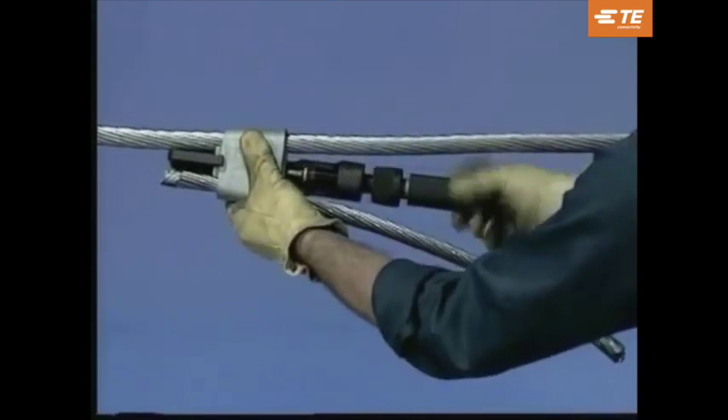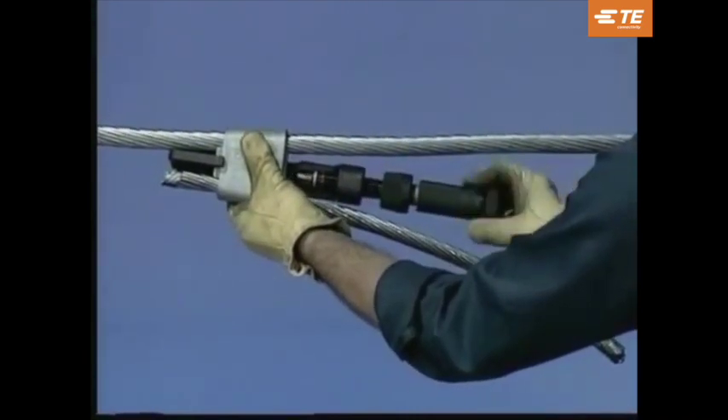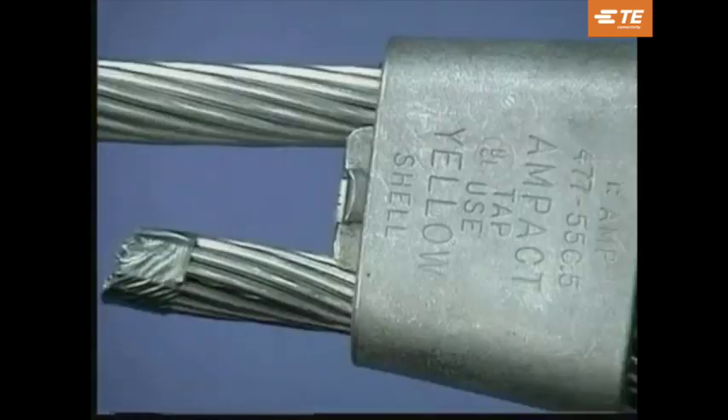All installed Ampact taps should be visually inspected for a locking tab feature. This visual indication ensures a good connection has been made.